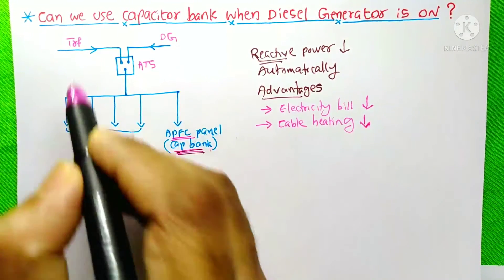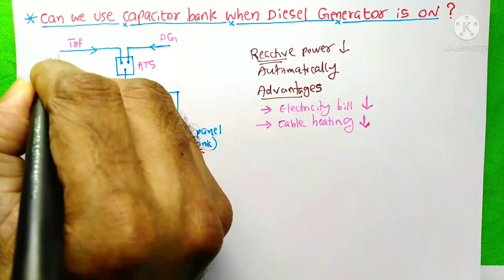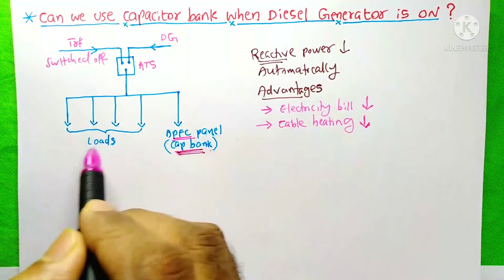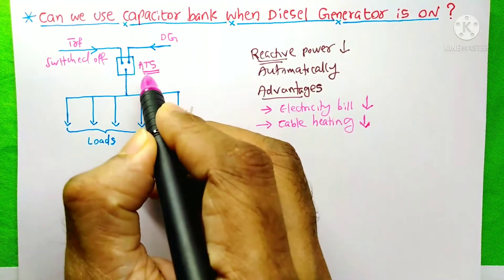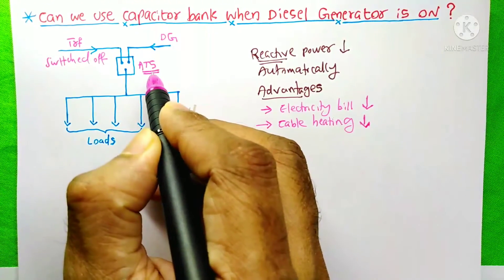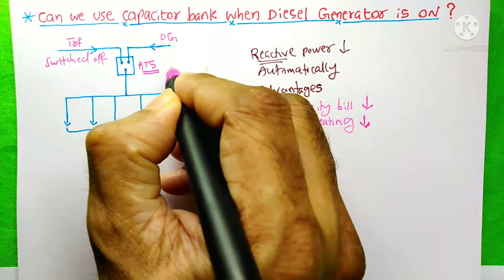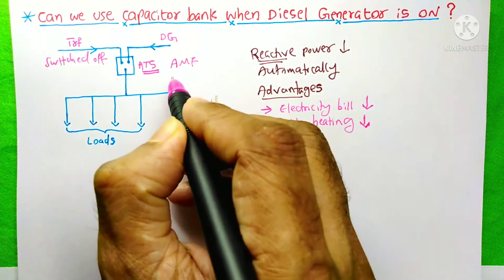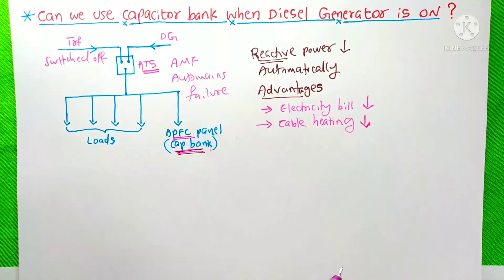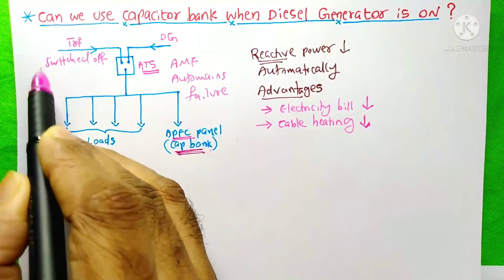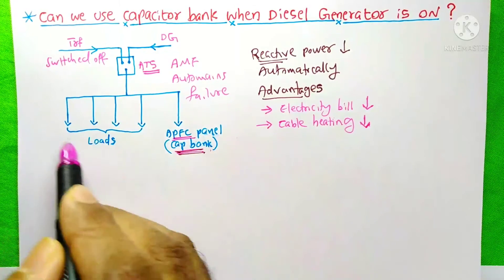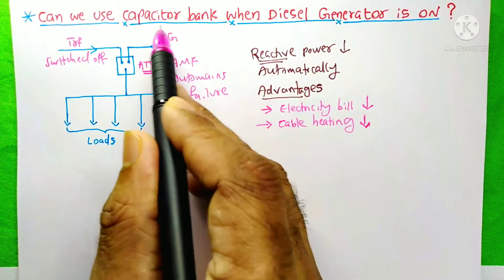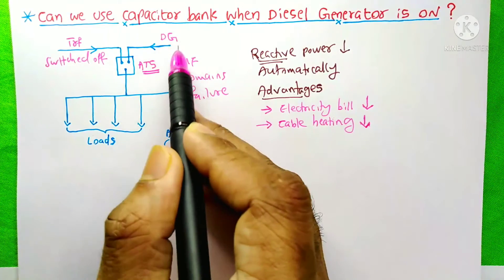Suppose this transformer is switched off and at this time we need power to this panel. The ATS — the automatic transfer switch — is associated with the AMF relay, that is the auto mains failure relay. Whenever this transformer is switched off, the AMF relay will send a signal to the DG and the DG will turn on automatically.